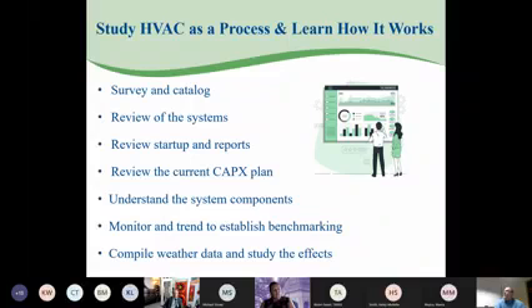We understand the system components and how they work. Monitor and trend the HVAC system to establish benchmarking for production processes. In graph form, how can we show that the temperature affects the process? Many times I've taken production data and put it beside temperature and humidity to determine when the production is affected the most. We compile weather data and study the effect on the plant HVAC systems. I've been running a spreadsheet that I've kept for almost 20 years, grabbing the monthly average on Weather Underground and then taking that and plotting it against utility bills to determine when something looks out of whack.